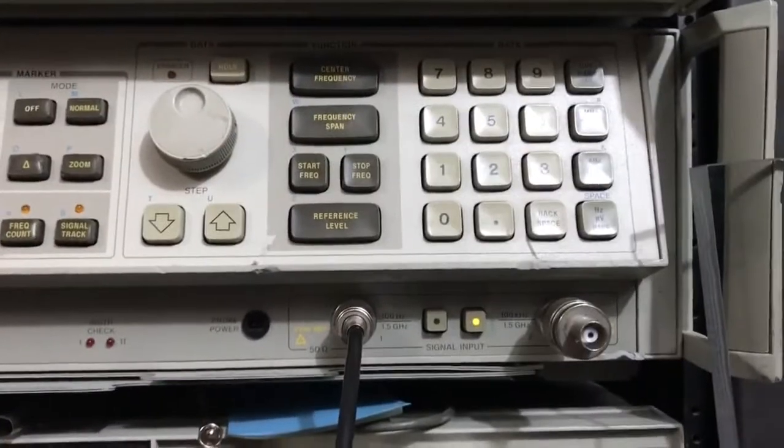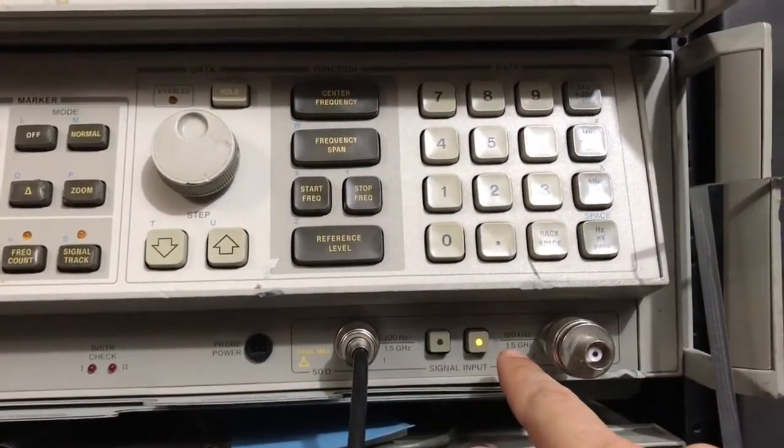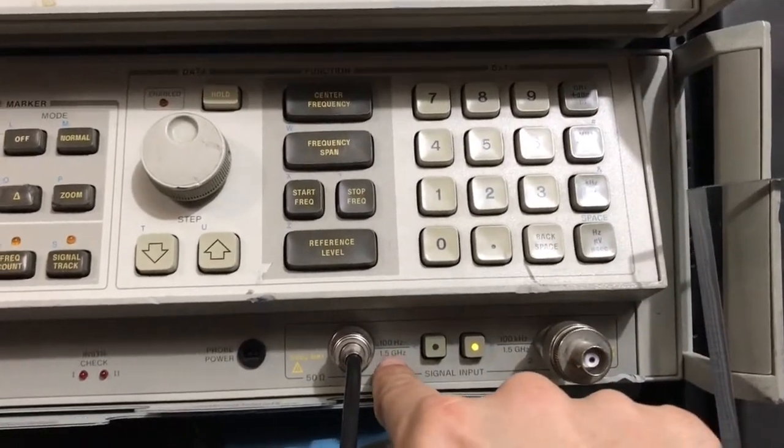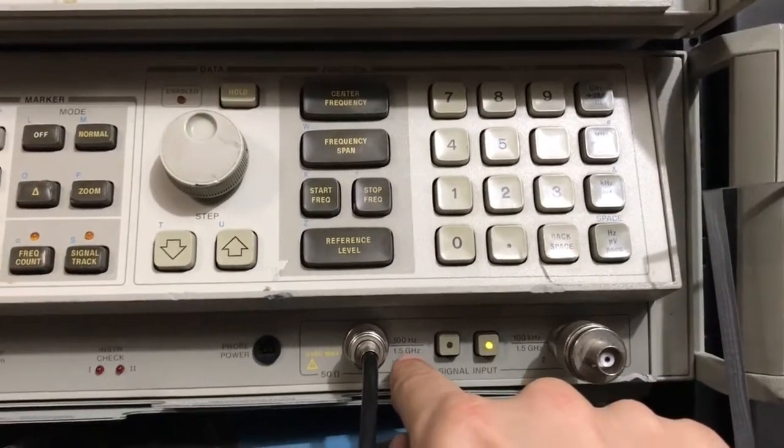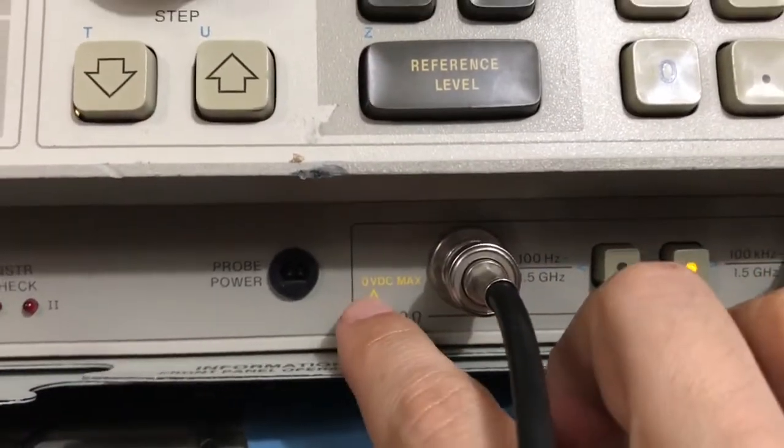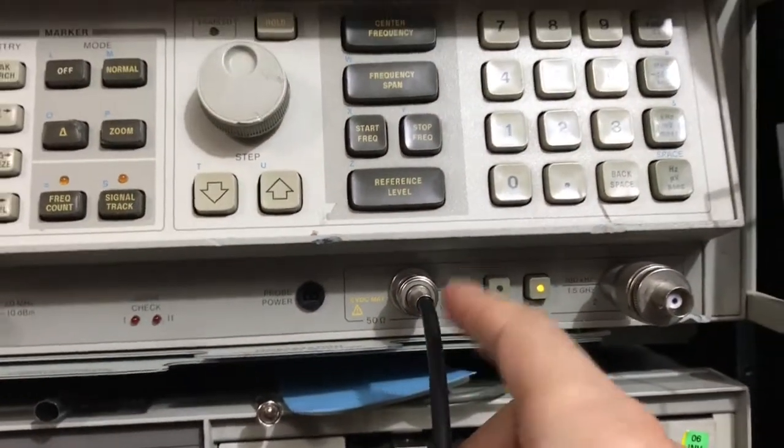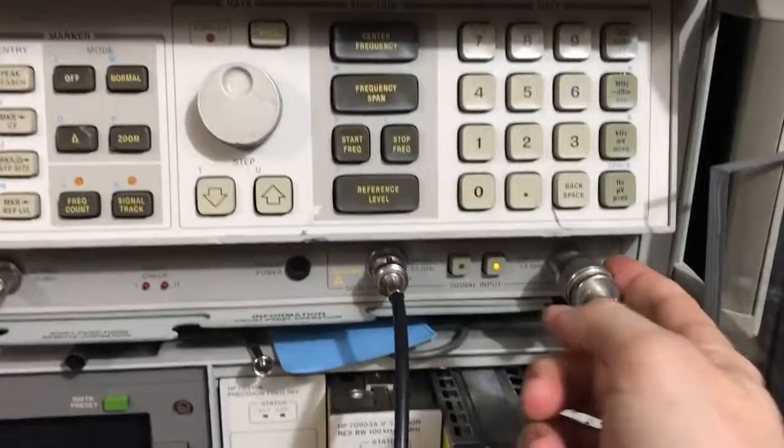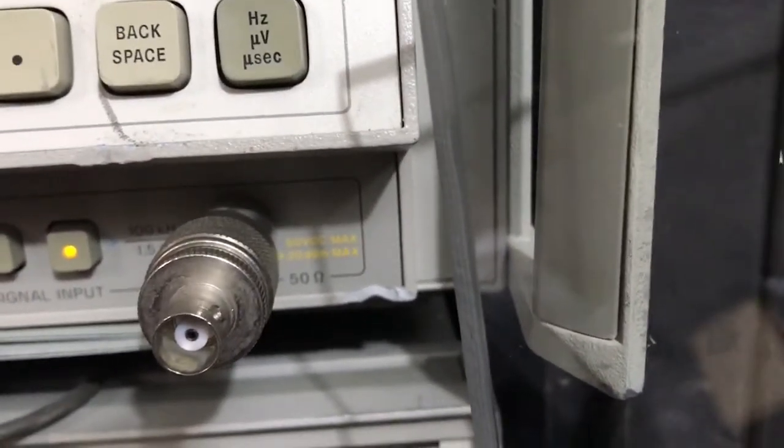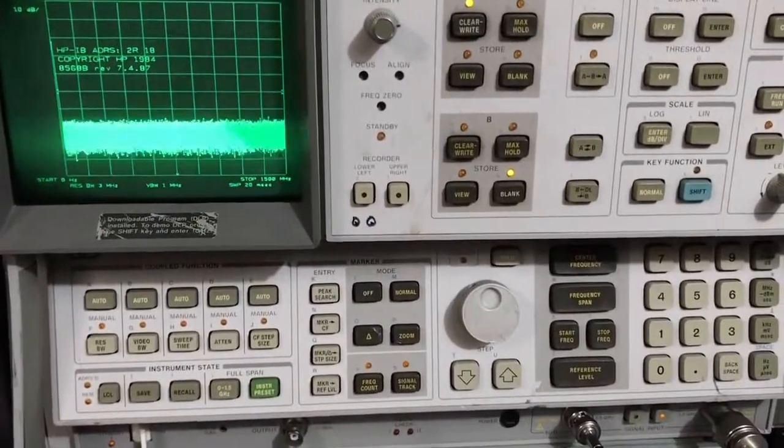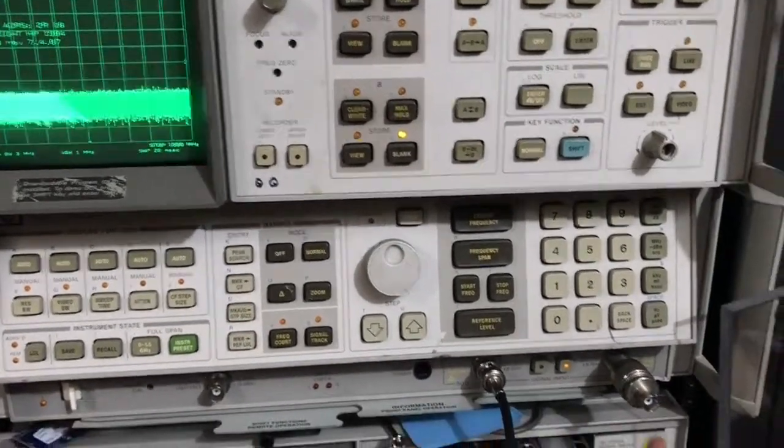And you'll notice here we have two inputs. The input on the right is the default selected. And it says from 100 kilohertz to 1.5 gigahertz. And the one on the left says 100 hertz, not 100 kilohertz to 1.5 gigahertz. And you notice 0 volts DC max. In other words, if you feed any kind of DC offset into this input, you're going to fry your input mixers. This input has a DC blocking capacitor on it, and it actually says 50 volts DC maximum there. So that blocking capacitor will take away some DC. I wouldn't feed any DC into it regardless, but at least you're a little bit safer.